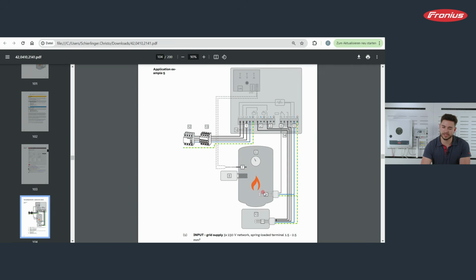Now, both of these can be dynamically controlled, but we must not forget one important thing. One outlet, the first phase, is dynamically controlled, so we need to make sure that this one is bridged onto our multifunctional relay. And from this multifunctional relay, we then go from normally closed to heating rod number 1, and from the normally open, we go down to heating rod number 2. By this measure, we make sure that both can be dynamically controlled. Very, very simple and effective. I don't need an external relay for that. I can make use of this multifunctional one.